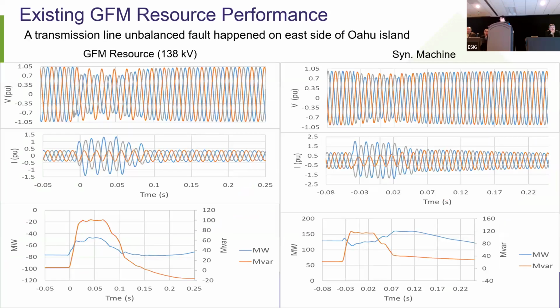This is about a fault, so there's no generation trip. This is another event that happened in Oahu. It's a transmission fault. The fault happened on the east side of Oahu, and the resources shown on this slide and the following slides are all on the west side of Oahu. First of all, it's not a very severe event. There is impedance involved in the fault, and it's an unbalanced, line-to-line fault.